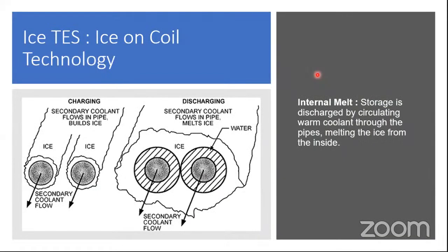So while understanding types of ice thermal storage, we have ice on coil technology as well. There is ice on coil technology, in which there are further two categories: one is internal melt, and the other one is external melt. Internal melt is, see, in this case, there are polyethylene tubes in which the brine solution flows at negative temperatures, let's say at -5 degrees centigrade, and around this tube is water.